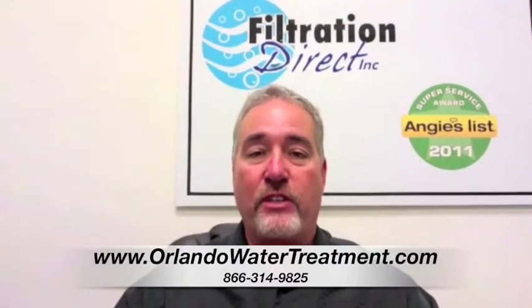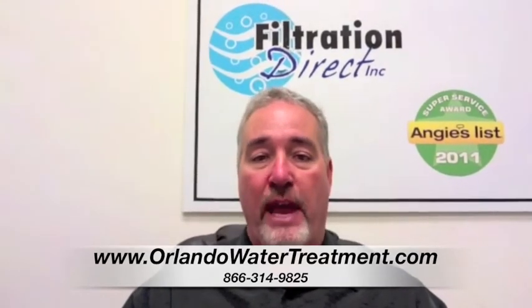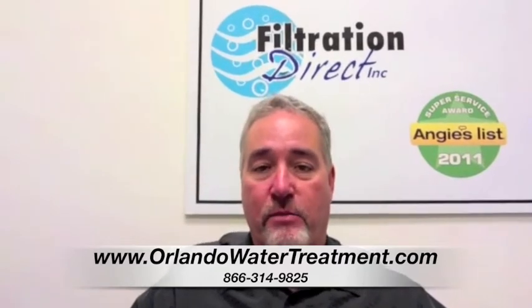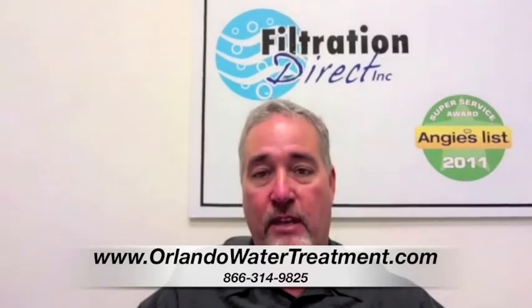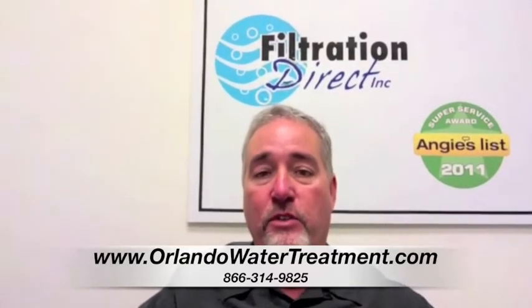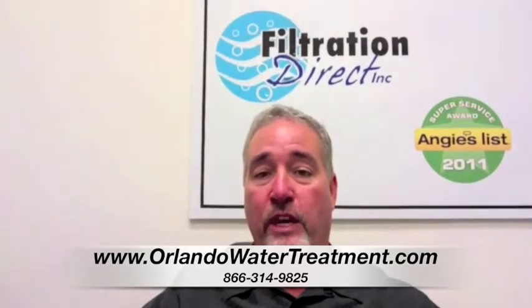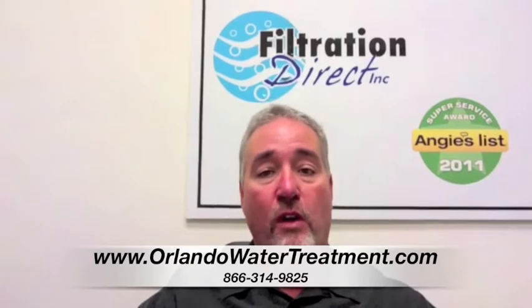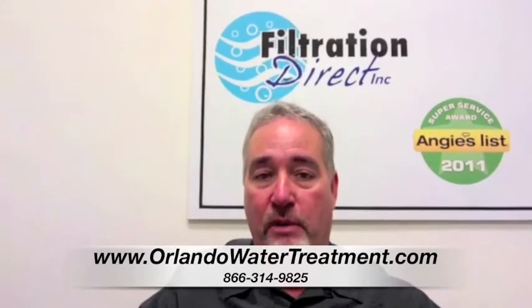During regenerations, the systems, and they're pretty much all the same, go into what's called the backwash. At that point, they're bypassing the system and they're going to draw a brine solution into the resin tank. The brine solution is going to mix with the resin that's in there, which are negative and positive ions, and they're going to remove all of the particulates that the system has collected by reversing the process.